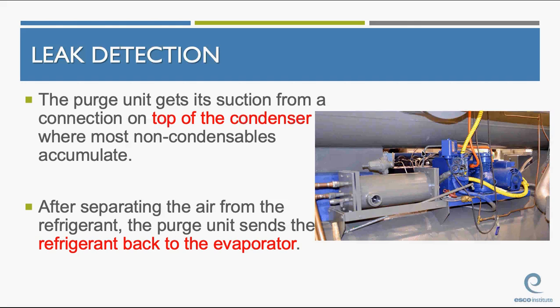The purge unit gets its suction from a connection at the top of the condenser where most non-condensables accumulate. That is a question on your Type 3 EPA exam. The purge unit gets its refrigerant pulled out of the top of the condenser. After separating the air from the refrigerant, the purge unit sends the refrigerant back to the evaporator. Guys, let me repeat this. The purge unit pulls its suction side from the top of the condenser. After separating air from the refrigerant, the purge unit sends the refrigerant back to the evaporator. So basically, the purge unit, for the amount of refrigerant it pulls, bypasses the entire condenser metering device, and it goes directly back to the evaporator. It has the pressure differential. It helps the purge unit work properly.